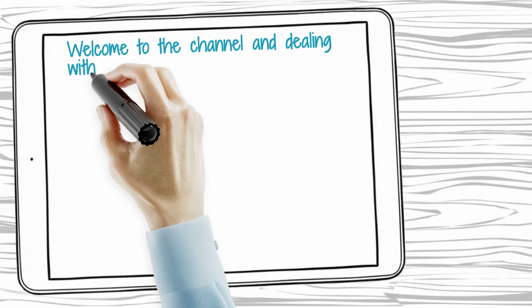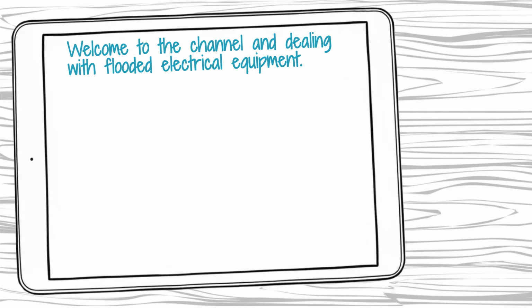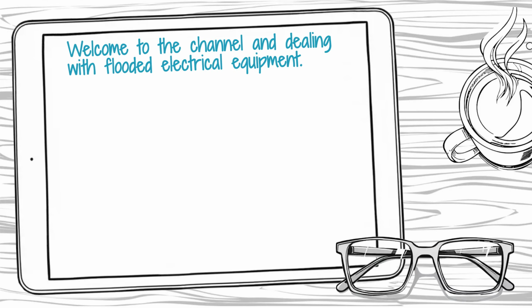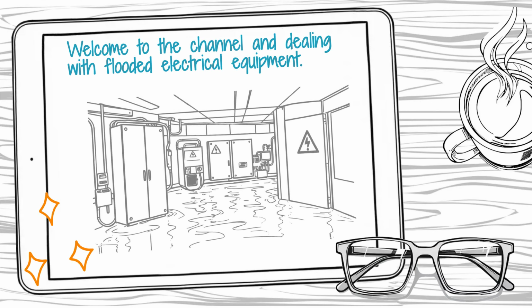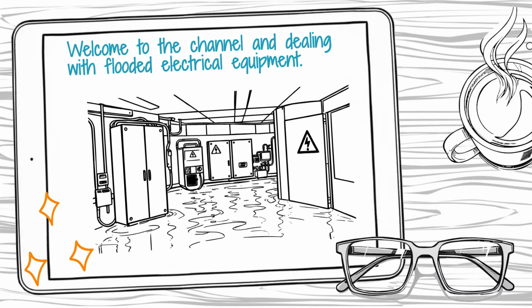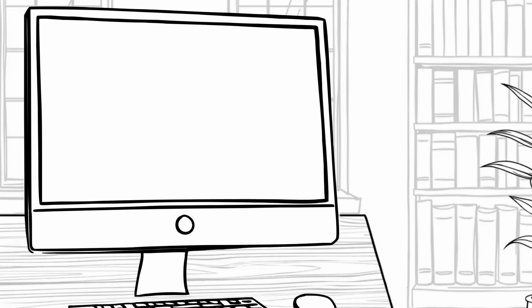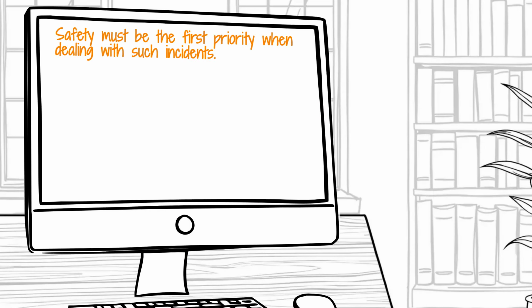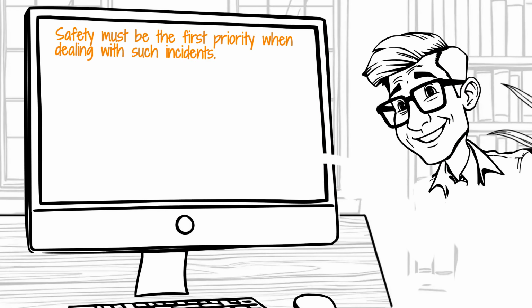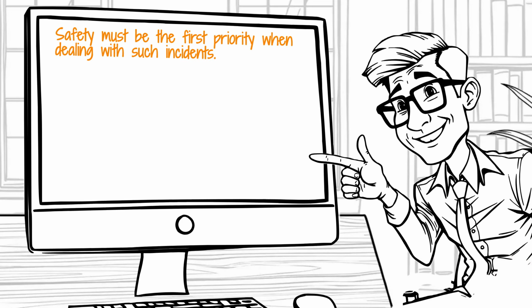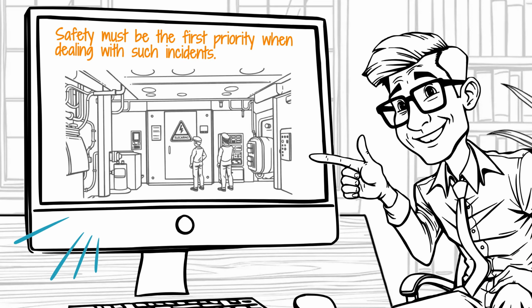Safely dealing with electrical equipment that has been affected by flooding or severe water ingress on a ship. Water and electricity create an immediate, extreme hazard: the risk of electrocution, fire, and extensive equipment damage. Safety must always be the first priority. The first and most vital step is isolation of power. Before approaching the flooded area or the equipment, the power supply must be secured.